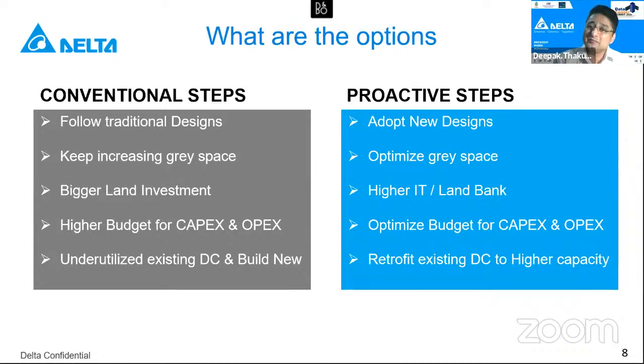That's one of the things we help our customers to do. And higher IT for land bank. The example which I gave: either you keep on increasing the land bank, or you increase your IT utilization of the land bank by having a better, optimized design. So optimized budget is one of the options. And by optimizing CapEx, you can also optimize the OpEx, as you will see in the subsequent slides. And the retrofit of existing DCs to higher capacities. Now you cannot kill your existing DCs just because they were designed 5 years back. 5 years back is not so long ago, but at that time the demand was not that huge. But your current existing data centers are sitting on a premium land bank. So how do you convert those into a larger IT? That's where the new way of thinking is coming.